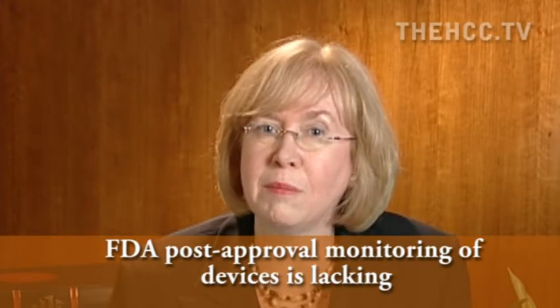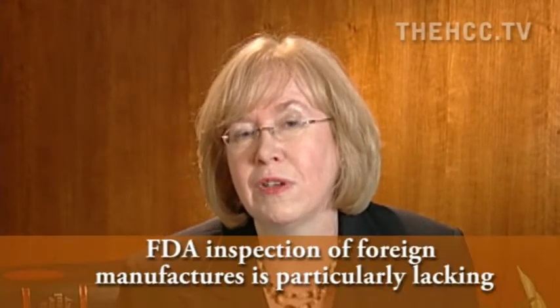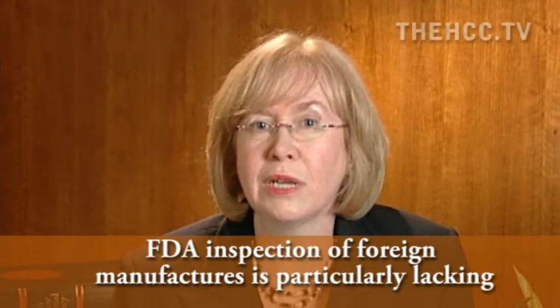Now, the device regulations are set up on the concept of a least burdensome approach to the manufacturers so that FDA can only require the minimal information that it believes is necessary to clear something for market. But that system relies on substantial post-market review by FDA. FDA is expected to be reviewing annual reports that are submitted by manufacturers. They're supposed to be reviewing adverse event reports, and they're supposed to be conducting inspections. We also know, though, that FDA has not been able to do all of those post-market activities. They're not able to review all of the adverse event reports that come in, and they're significantly behind on their inspections of manufacturers, particularly those foreign manufacturers that make up an increasing portion of the manufacturing of medical devices for the U.S. market.